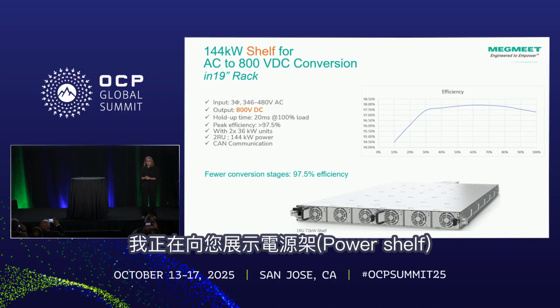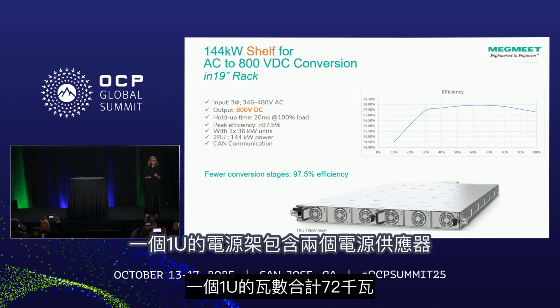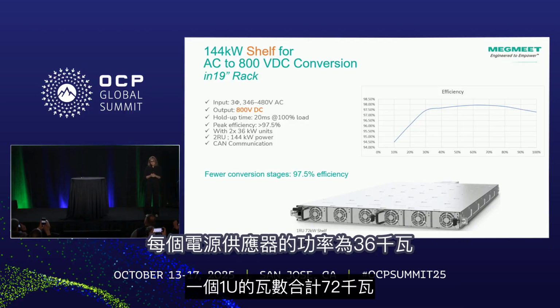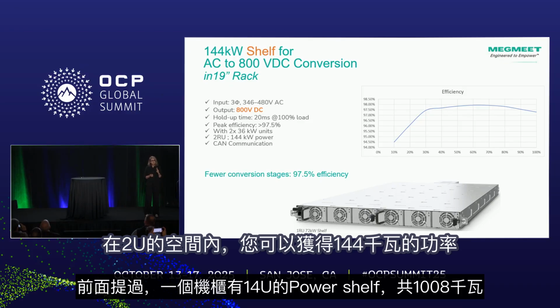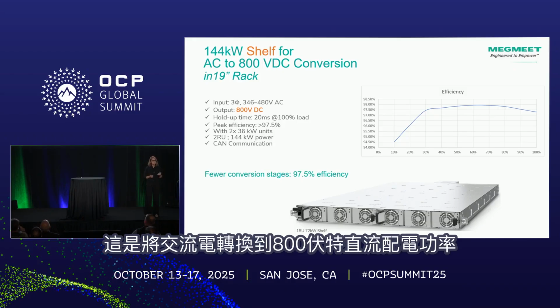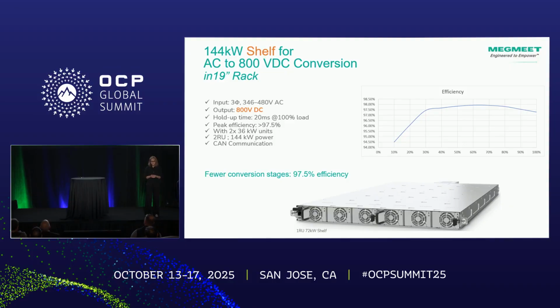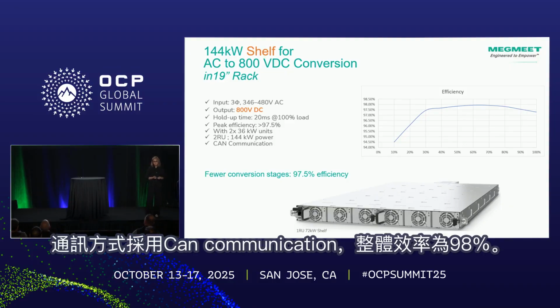I am showing you the power shelf. 1U power shelf is 2 power supplies, and each power supply is 36 kilowatt. In 2U, you get 144 kilowatt, which is the AC to 800 volts DC distribution conversion. Communication is on CAN bus, and this is 98% efficiency.